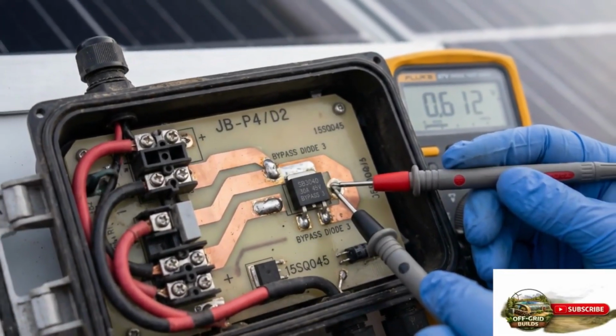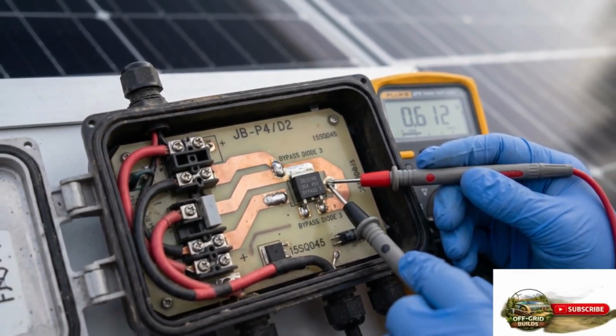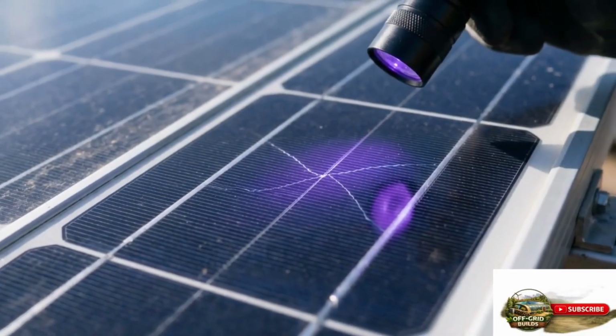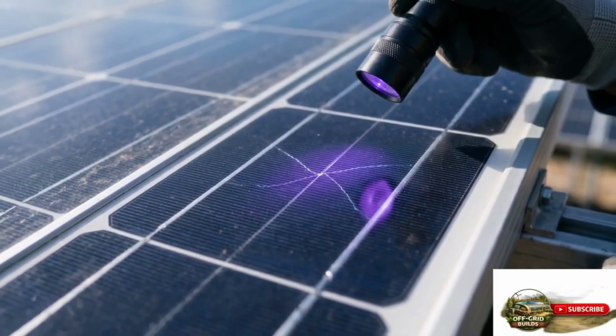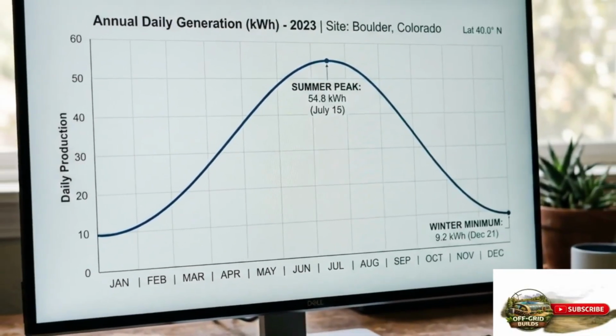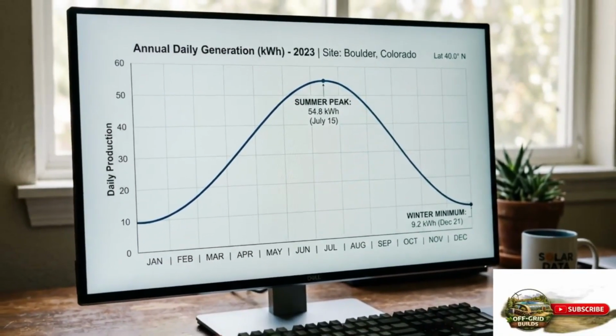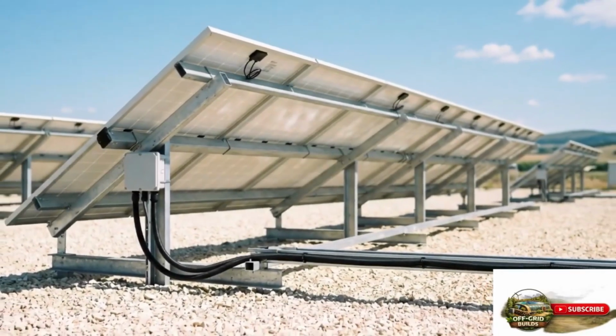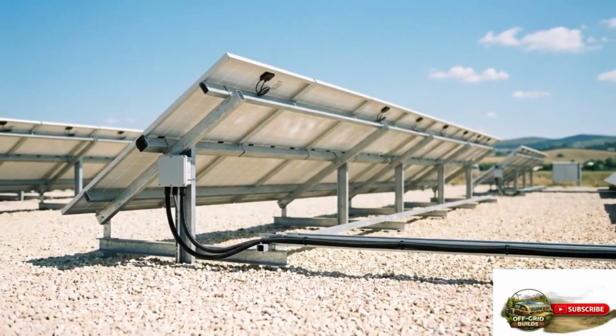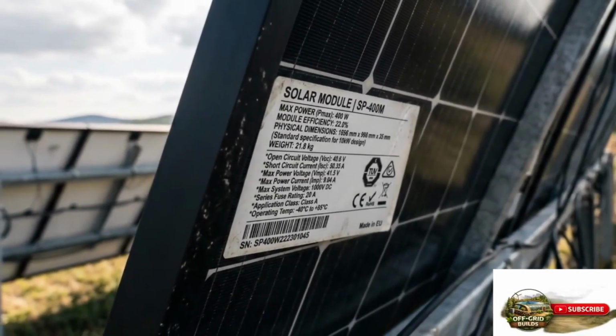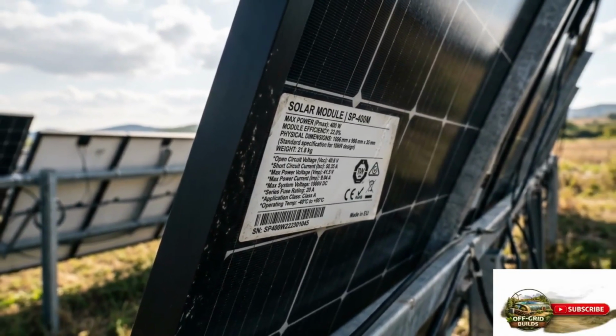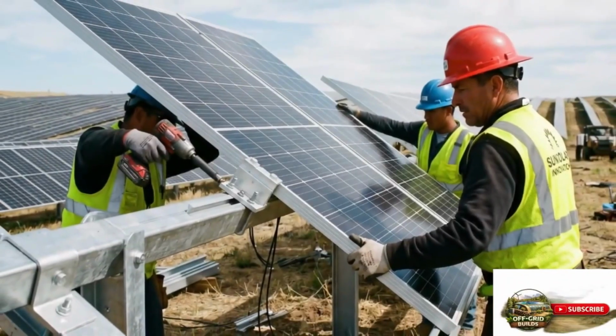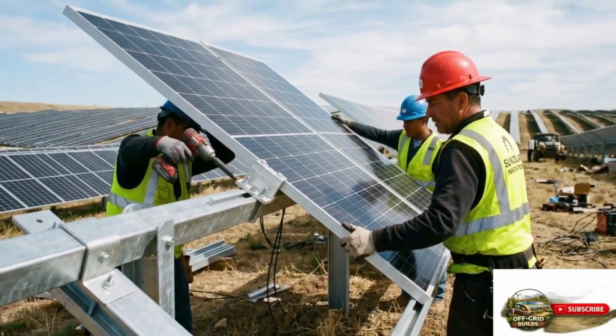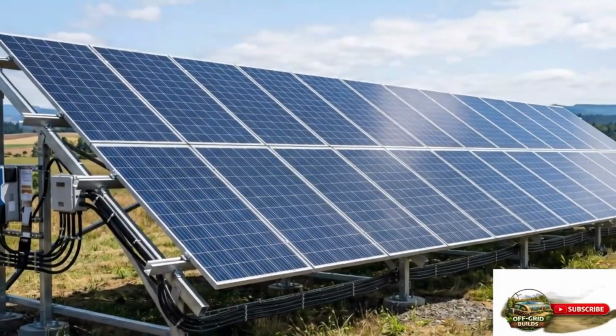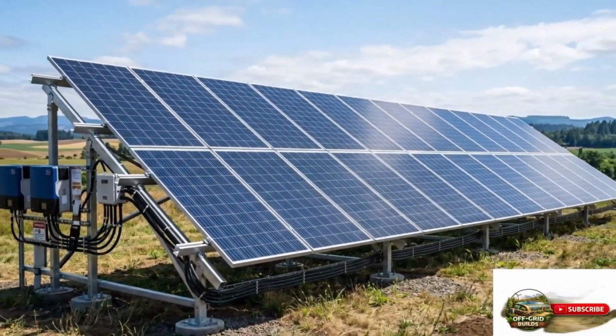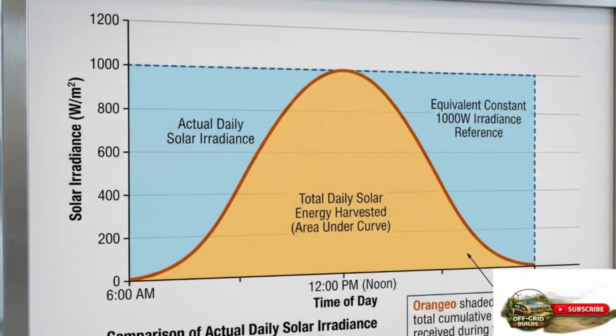Panel ratings are given under standard test conditions, which use a specific light intensity of 1,000 watts per square meter, a panel temperature of 25 degrees Celsius, and an air mass coefficient of 1.5. Real-world conditions rarely match STC exactly. Hot panels produce less power than cold panels, which is why desert installations sometimes underperform their STC ratings during peak summer heat despite having abundant sunlight. Cold, clear, winter days in high-altitude locations often produce conditions close to or even exceeding STC, and panels in these conditions may briefly produce output near or at their rated wattage.